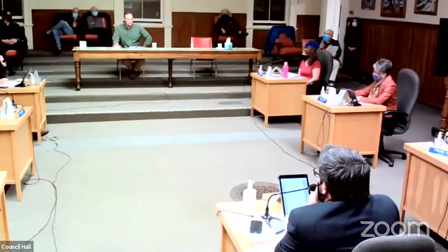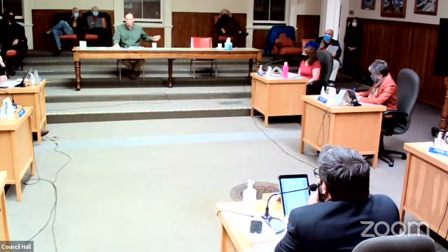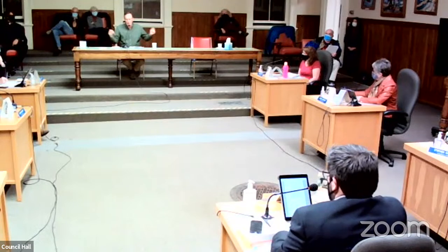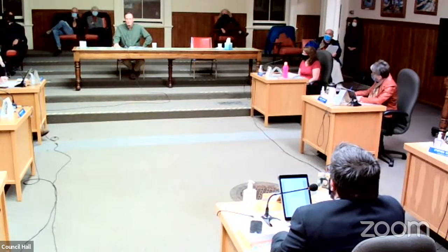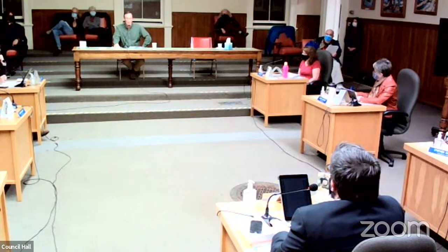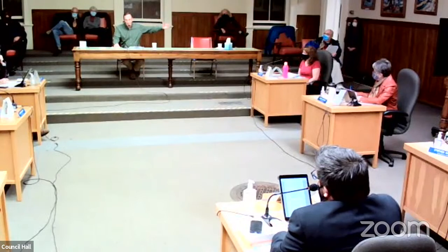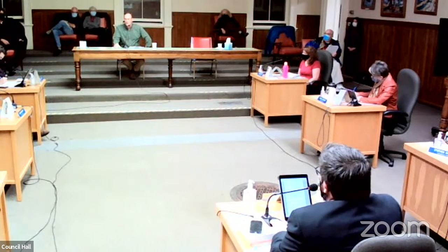Now, whether that reaches other long-term goals, that's a different question, I think. So I'm not against using that technology. I certainly had doubts when I started this little journey as well. So in terms of looking at a different technology and with different goals, I think more background work would need to be done to fully assess that, because I have serious doubts about the price tag, to see whether that's really a $10 million project or more like a $15 million project, and what's our limit. It's great to have that, but I'd love to drive a Rolls Royce, but I can't afford one, you know. At what point do we say, okay, this is achievable and that's not? I don't know what the answer to that question is, but I think that question is attached to that option. That's not just in terms of capital, but also in terms of operations, a much more intense plant to operate, the membrane system. So we need more staff, et cetera, for that.